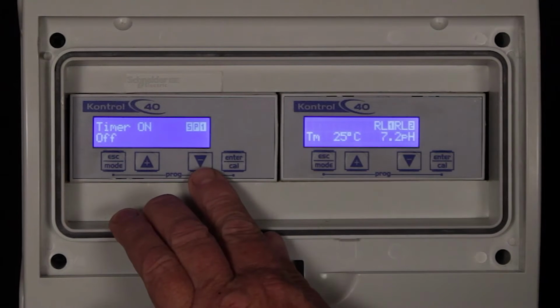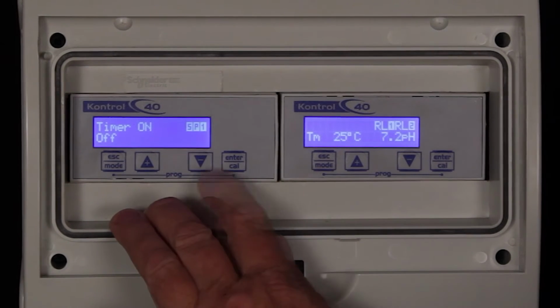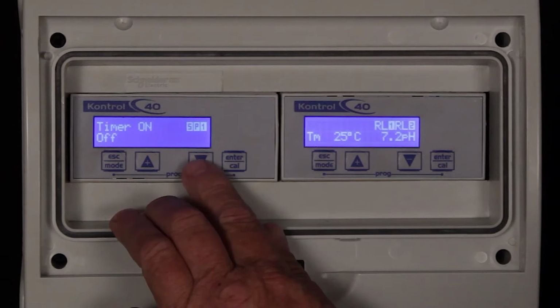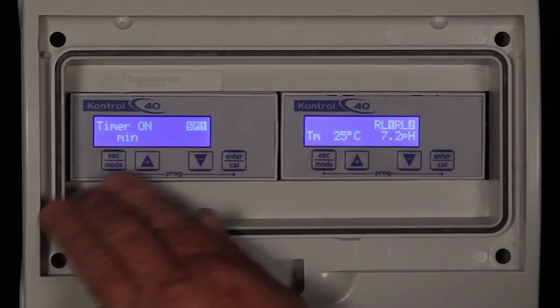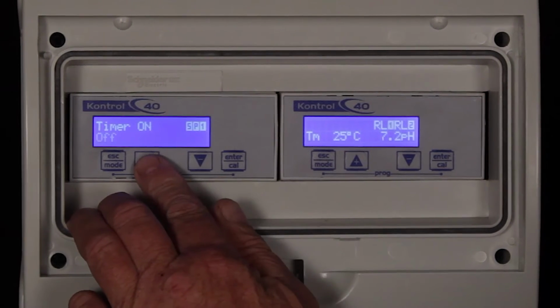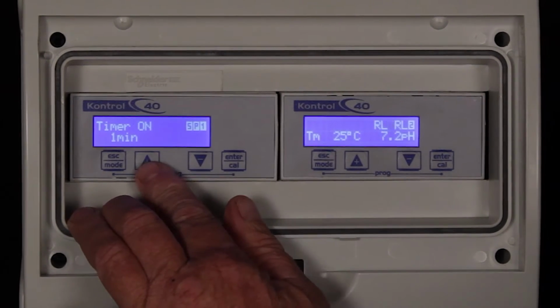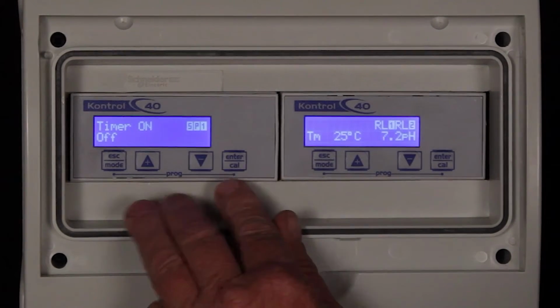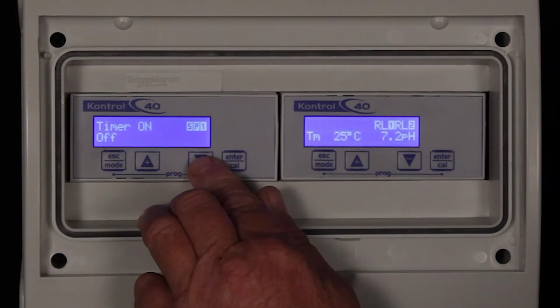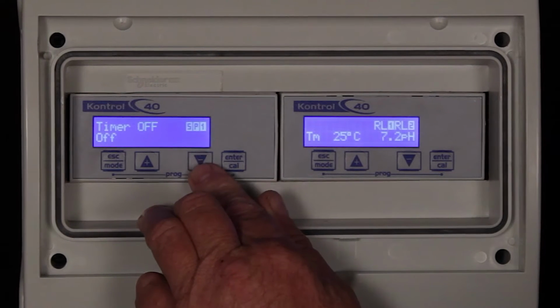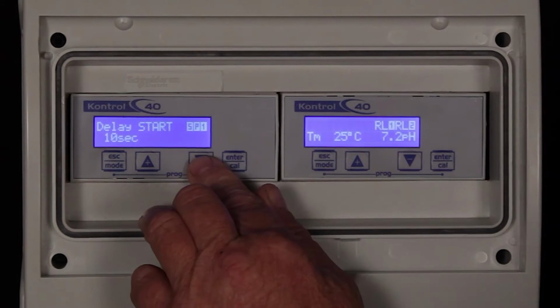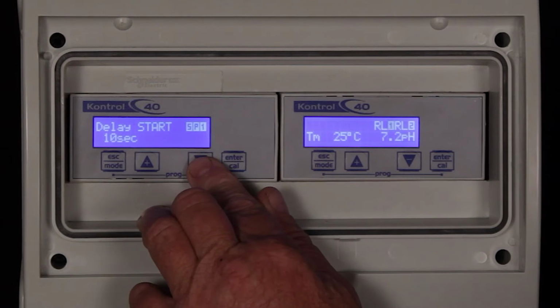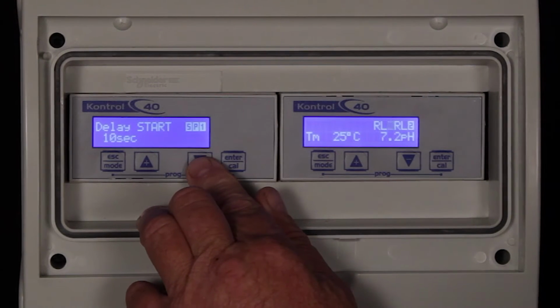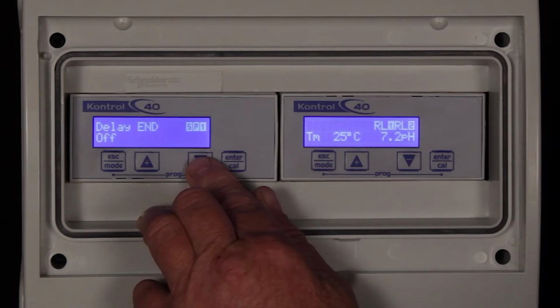The on timer can be set so you can limit for how long the pump must switch on. Values are either off or a range from 1 to 480 minutes. For the purposes of this tutorial, it is turned off. The off timer can be set so you can limit the off period in between dosing cycles. You can set a time delay for the pump to start. The reason for this is to eliminate quick fluctuations on false signals. You can set up a time delay, but I normally switch the delay off.